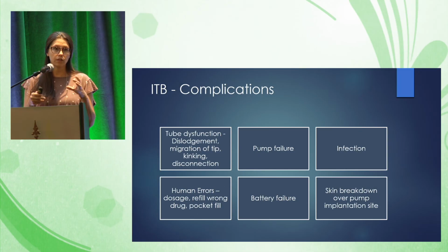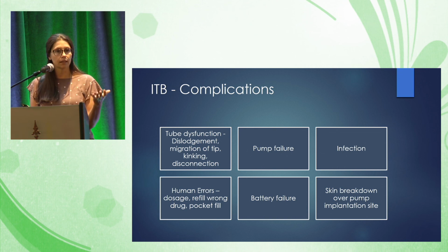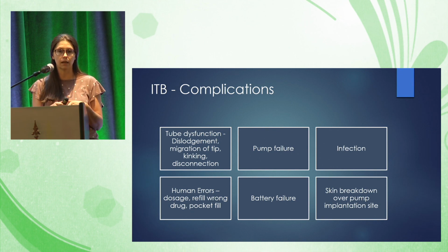There are complications, and I want you to be aware of that, with the intrathecal baclofen therapy. There are a lot of resources in place to really mitigate all of these from happening, but it is a possibility. It's rare, but it's a possibility. So there can be issues with the device itself. There's a computer chip. It's electronic, and so electronics may fail. It's got a tube that goes from the device through the body and into the spinal canal, and so that tube has the possibility of moving, cracking, kinking.